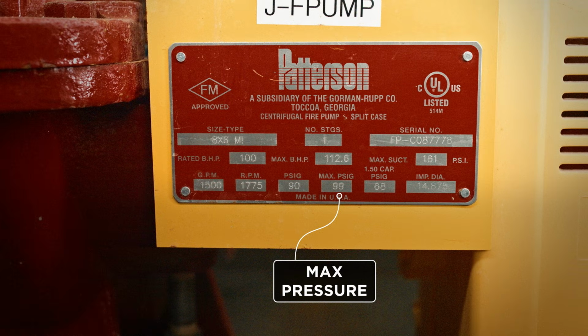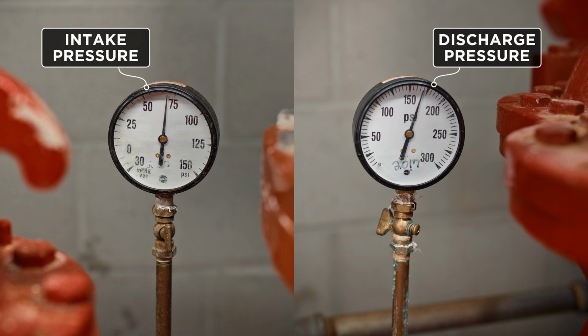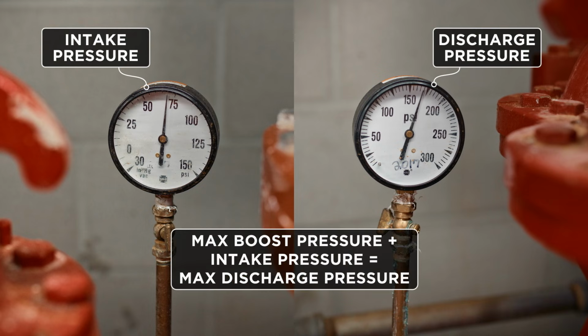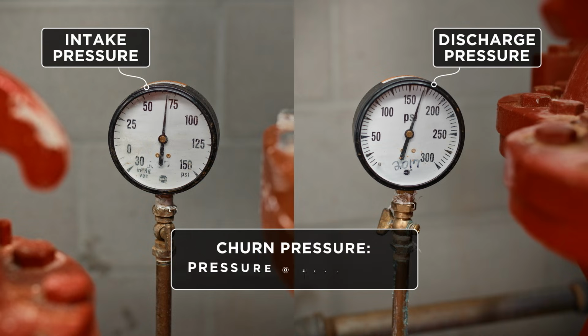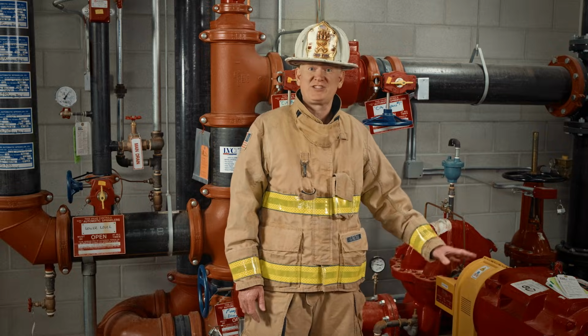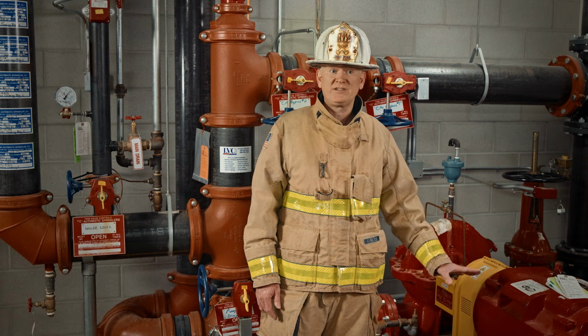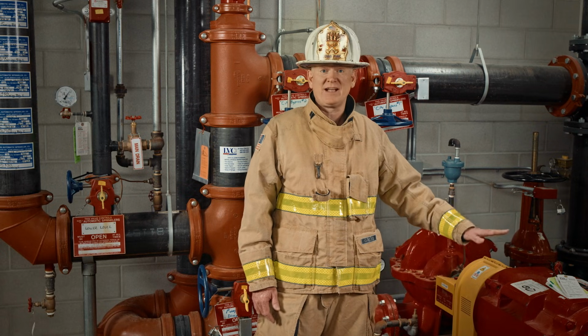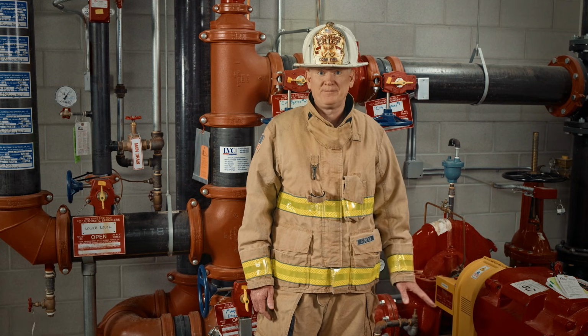If we take that and add it to the pressure coming off of the municipal supply from the street, that gives us the maximum discharge pressure we would ever expect out of this pump installation. That's referred to as the churn pressure, or the pressure at zero flow. Fire pumps operate at a fixed speed. They're never going to go any faster. That's the maximum pressure they can deliver.